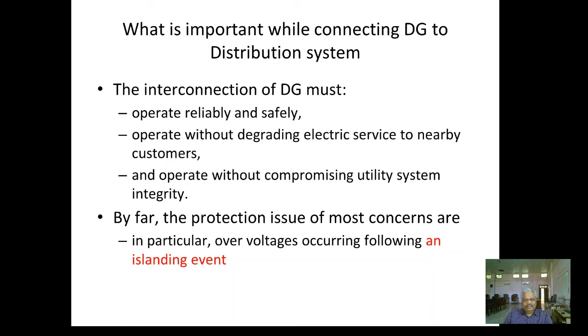Now we will see. Island, you can call it an isolated power system. And when we say isolated, in today's COVID days, isolated means quarantine, or isolation for precaution. The same thing is there. In geography, an island is a land body disconnected from the mainland and separated by water. We know this. Generally, many people are interested to go to an island for a tour. Second, in electrical concern, an island is a small part of the electrical distribution network disconnected from the main grid due to an open circuit. It means when a breaker opens due to any reason, either outage, fault, maintenance, whatever it may be, then an island gets formed.